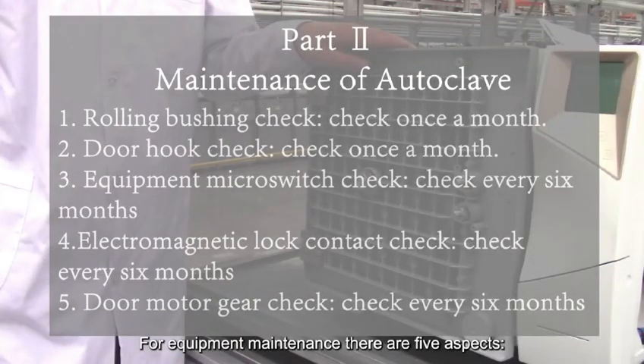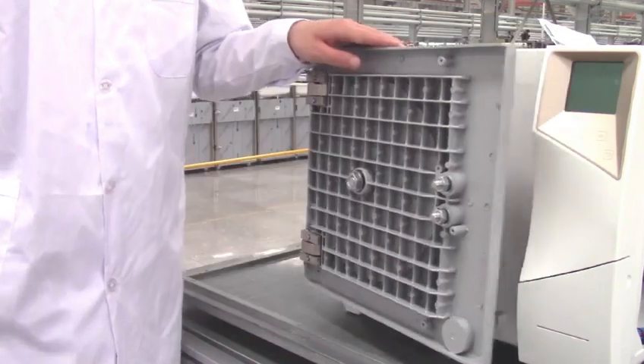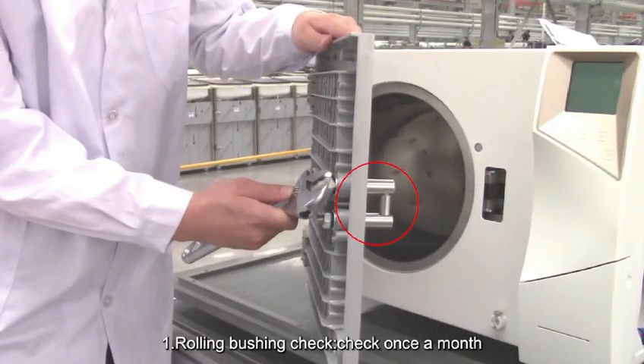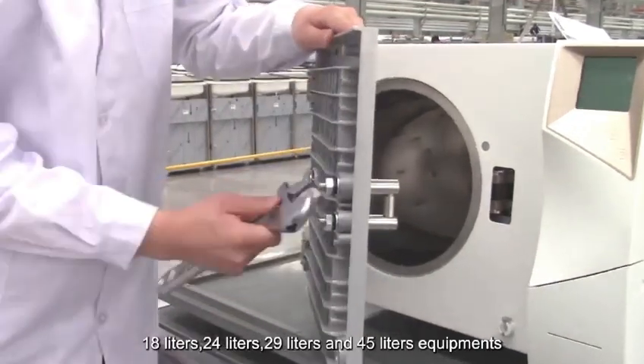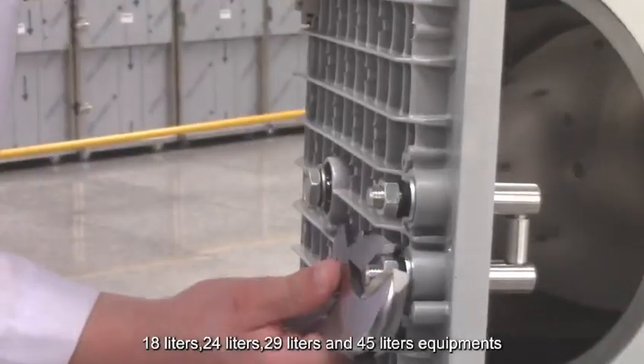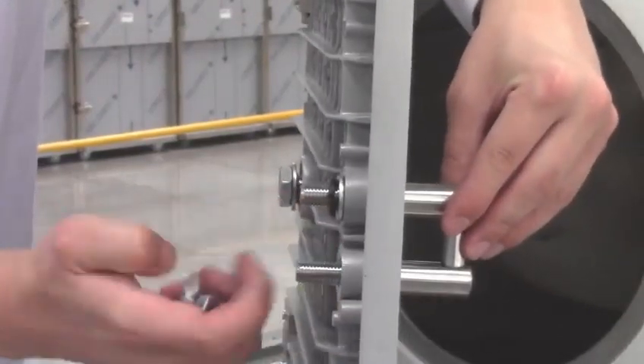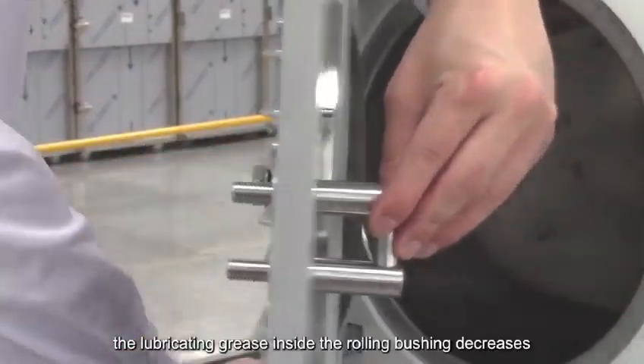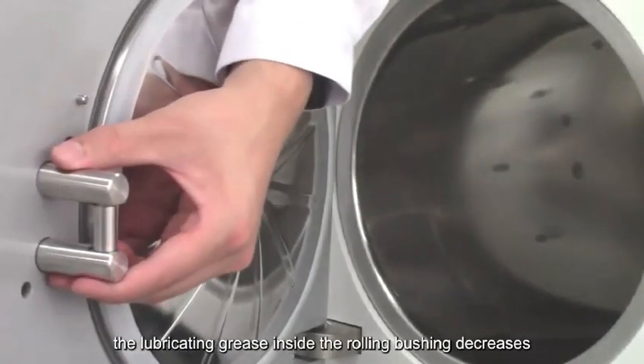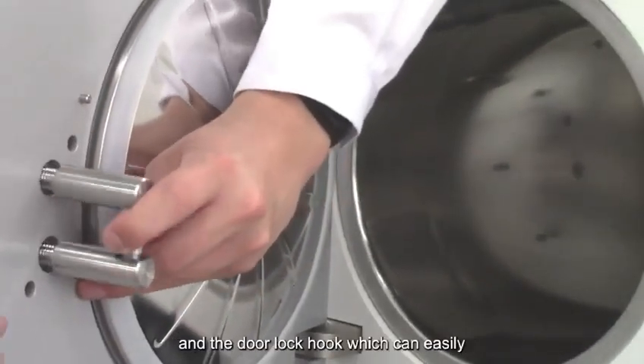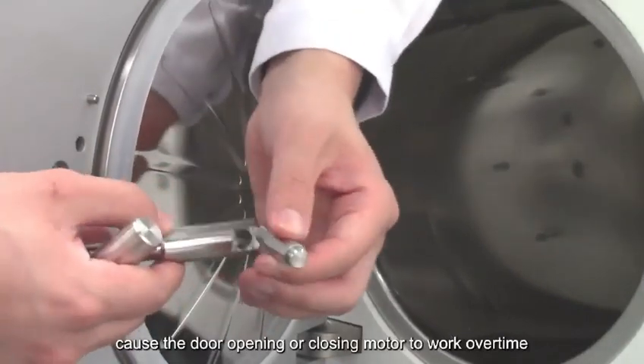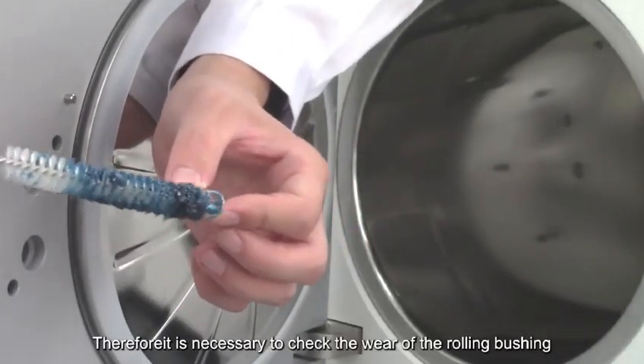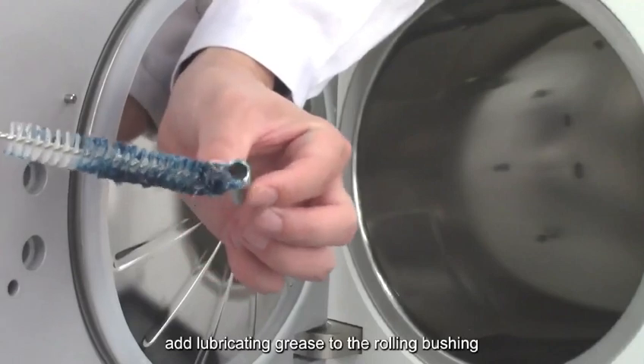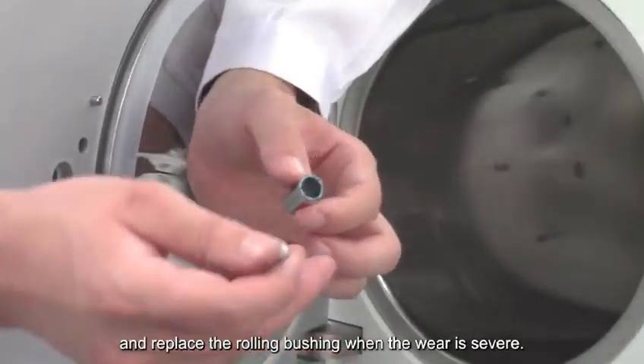For equipment maintenance there are 5 aspects. 1. Rolling bushing check. Check once a month. 18 liters, 24 liters, 29 liters and 45 liters equipment have a rolling bushing on the outside door. After using the rolling bushing for a period of time, the lubricating grease inside decreases, causing wear and tear between the rolling bushing and the door lock hook, which can easily cause the door opening or closing motor to work overtime. Therefore, it is necessary to check the wear of the rolling bushing, add lubricating grease to it, and replace it when the wear is severe.